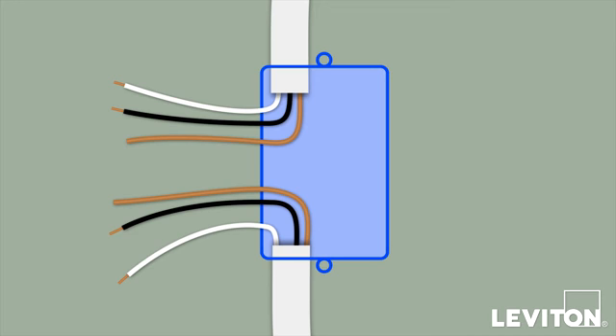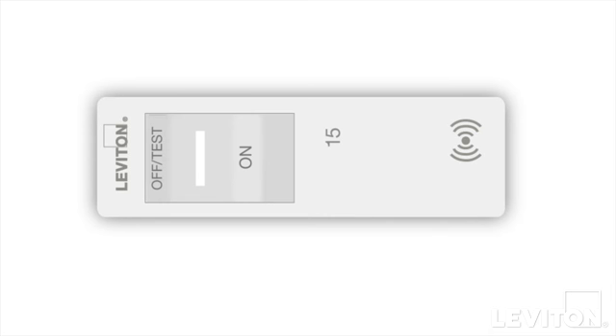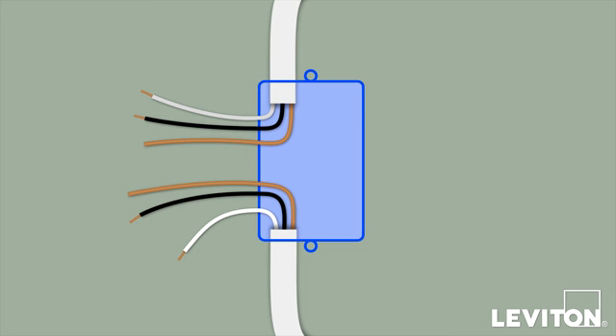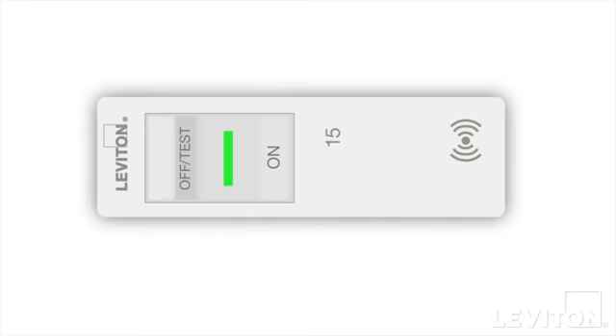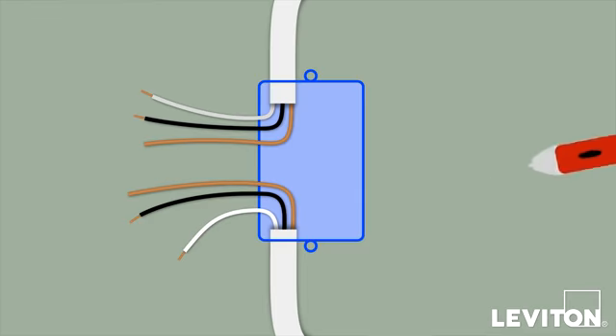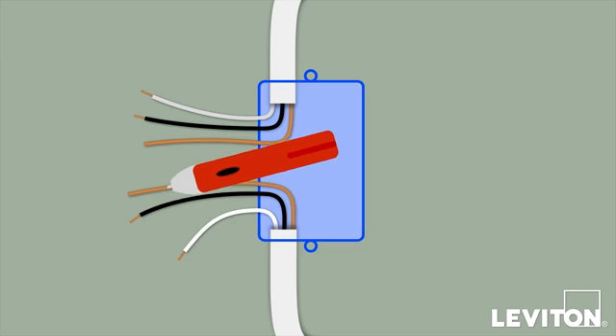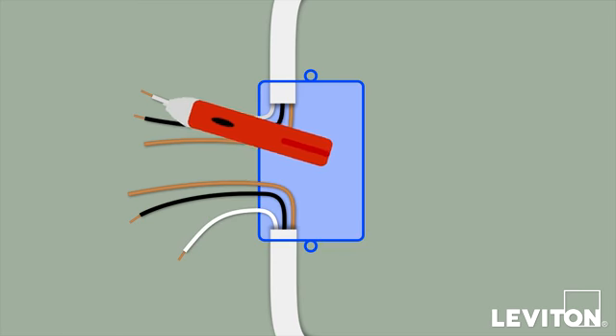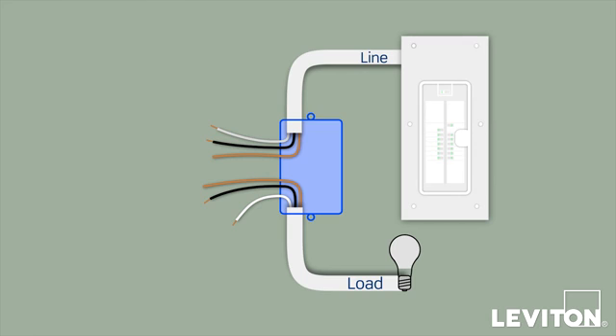Now we need to identify the hot wire. To do this, turn the circuit breaker back on. Carefully use the voltage tester to test each wire. The hot wire will be indicated by the tester. Once identified, turn off the circuit breaker to shut power and test to ensure that the power is completely off. Use a small piece of electrical tape to label the hot wire.